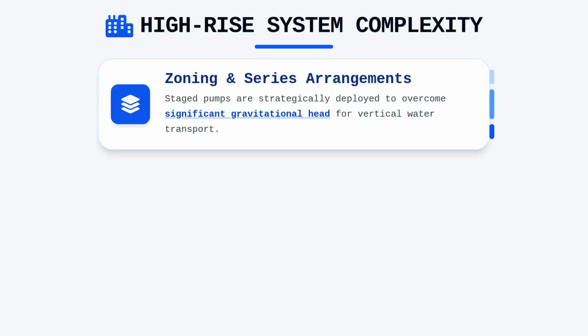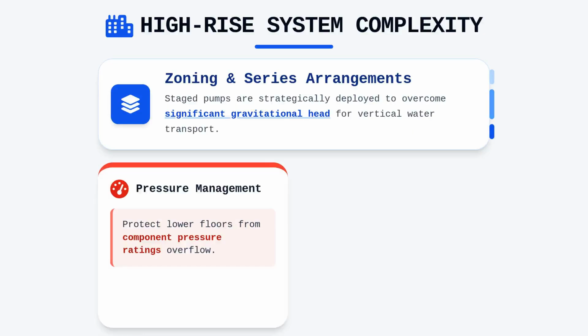Complexity of these systems increases significantly when we introduce high-rise zoning or series arrangements where multiple pumps are staged to overcome significant gravitational head. In such configurations, we must carefully manage the pressure at each zone so that we do not exceed the pressure ratings of the sprinkler components installed on the lower floors. This requires meticulous attention to the placement of relief valves, which act as a fail-safe to bleed off excess pressure if the pump drifts away from its design point.